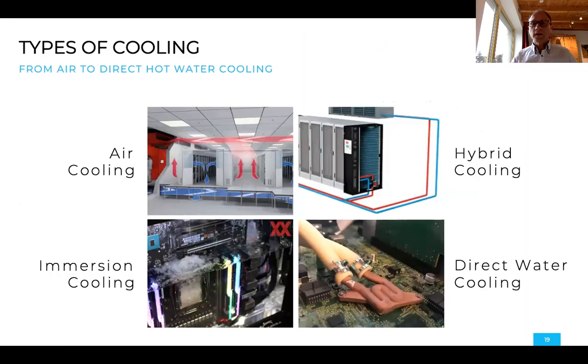Now that's something one can do, but I also want to show you what currently is done in classical data centers. So you have air cooling. If you do that right, you have a cold aisle and a warm aisle, and you have circulating air, and you have systems that cool down the air, and an air conditioning system is typically connected to that. There are systems with so-called side coolers, where you put coolers next to the servers, but still you need compression systems, classical air compression systems, to take the heat out of the air and then bring it to the outside. And especially in the summertime, you cannot do that without extra electrical energy.